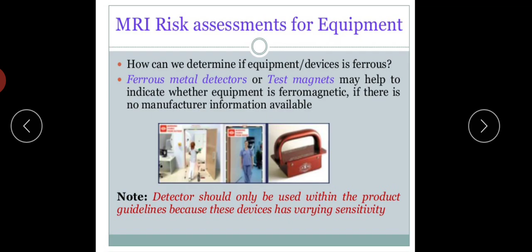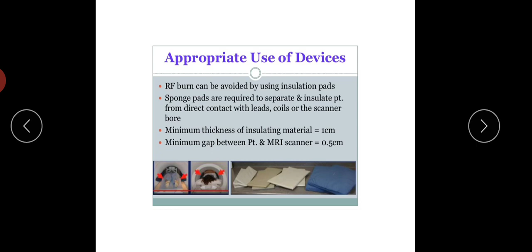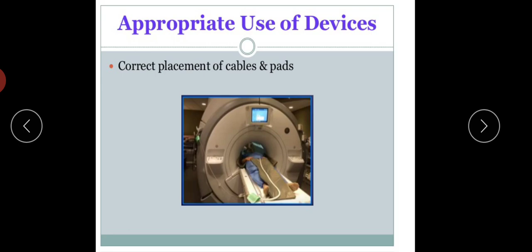Appropriate use of devices. RF burns can be avoided by using insulation pads. Sponge pads are required to separate and insulate the patient from direct contact with leads, coils, or the scanner bore. Minimum thickness of insulating material should be 1 cm and minimum gap between patient and MRI scanner is 0.5 cm. Appropriate use of devices means the correct placement of cables and pads like this.